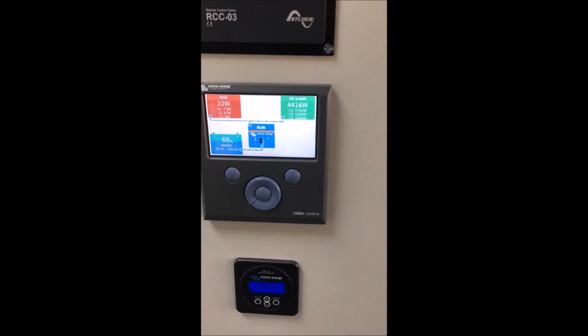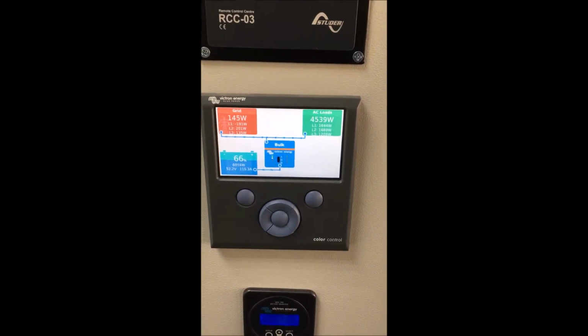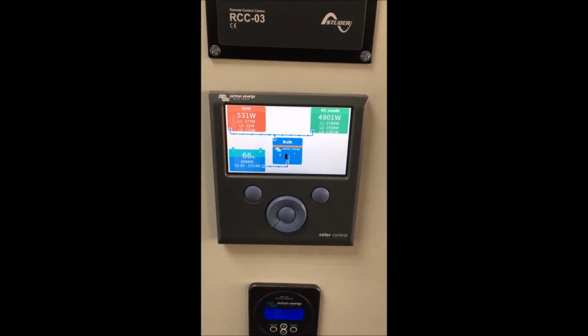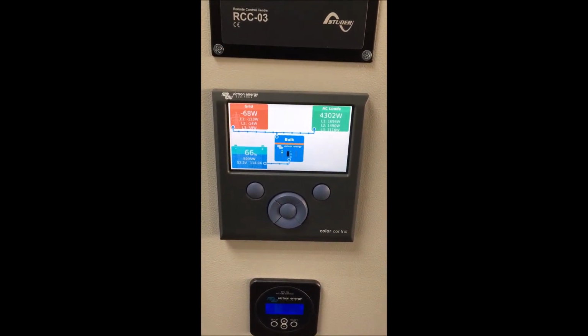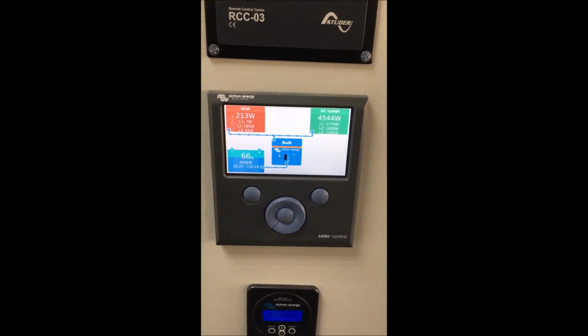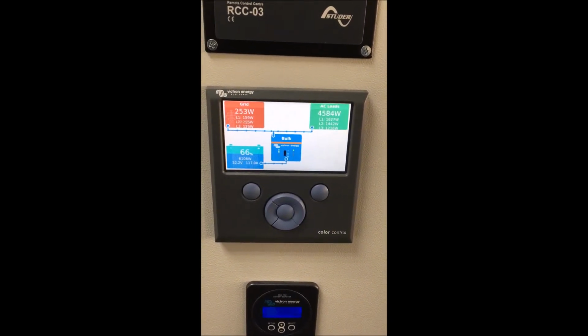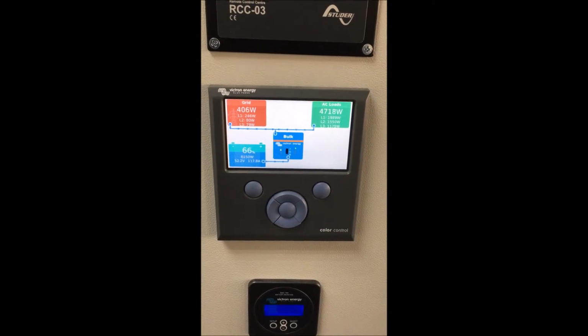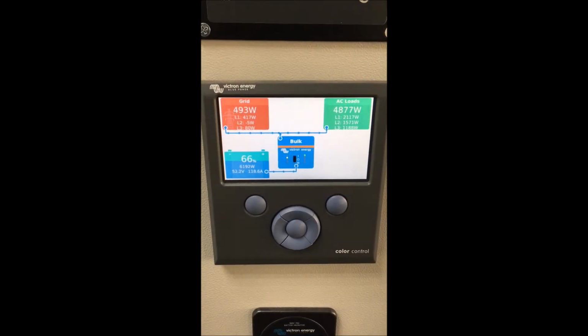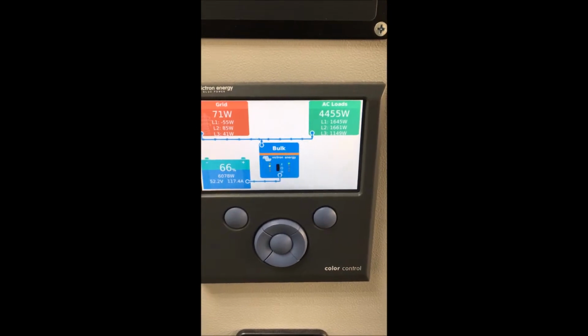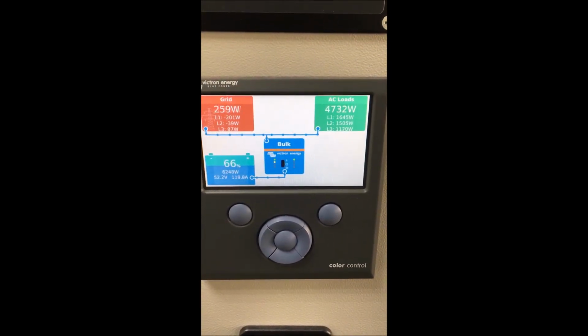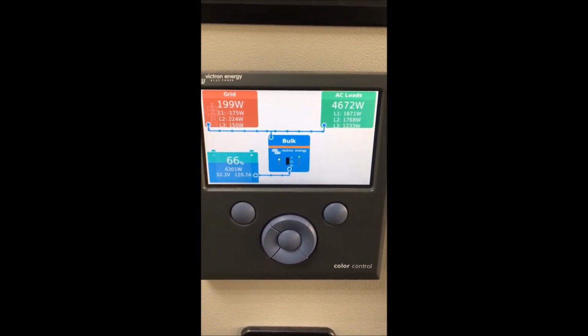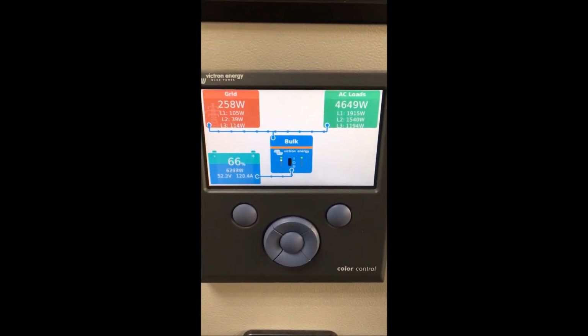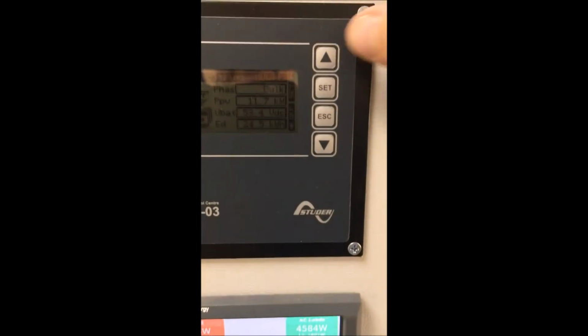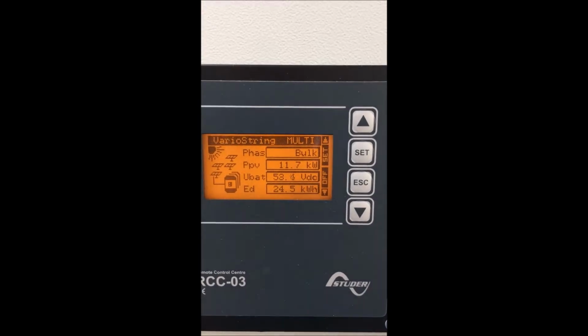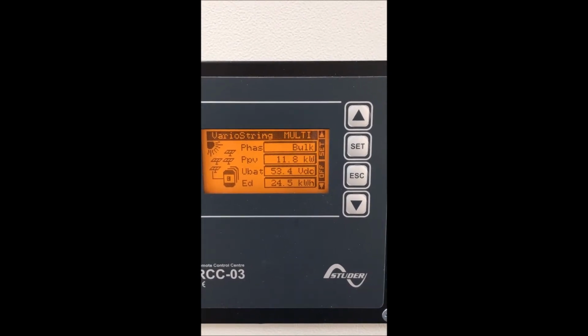With this system, we can manage the energy flow between energy generated by PV panels or energy received from the grid, the energy that's used by the load, and the one that comes into the battery or goes out of the battery. As we can see here on the display, we're now consuming about 4.6 kilowatts in the load. At the same time, we are storing about 6.3 kilowatts in the battery. This is because our solar system produces 11.7 kilowatt.